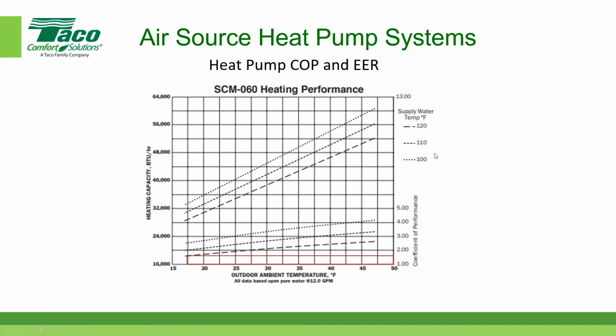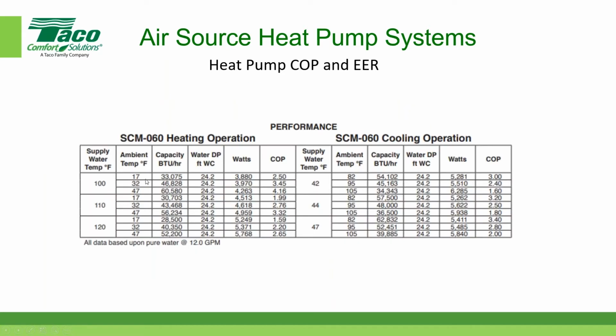Now, if you'll notice, if we're only making 100-degree water over here, that would be this top dotted line here at 17 degrees. That would mean we'd be making, well, there's 32, that's 40,000. So the difference between those two is 8,000. So that would be 36,000. So this at 17 degrees would be around 33,000. So we can go back to that other chart at 100 degrees Fahrenheit, 17 degrees. You can see right there it's about 33,000 BTUs per hour. And the COP begins to improve, even though the ambient temperature is still 17, but if we're making water at 100 degrees, the COP improves a little bit. Okay.